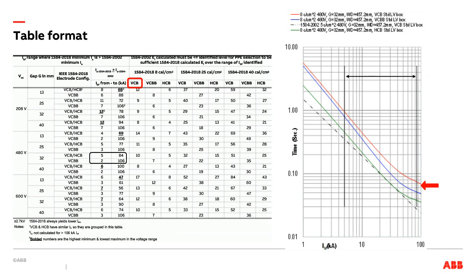The red line represents a VCB situation, the blue line represents VCBB, and the green line represents HCB. I plotted this line over here, so that's where the 5 calories came from. I kind of covered it up with the green. And of course, that black line is that value. Is this 480 volts? Yes, I'm sorry. That 5 is this line, because that's for 480 volts HCB. So that's the HCB right here. The 5 to 84 kiloamps is these two lines, HCB for the black line and for the colored line, and that's where the 5 calories come from. That's where these two lines touch.